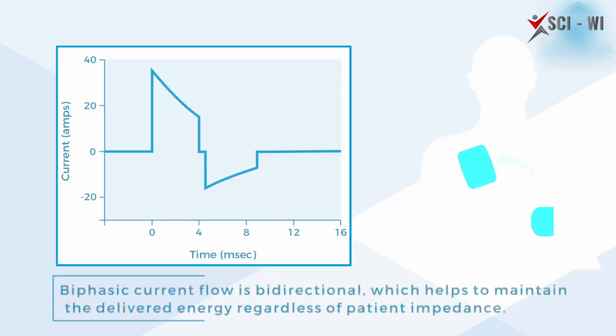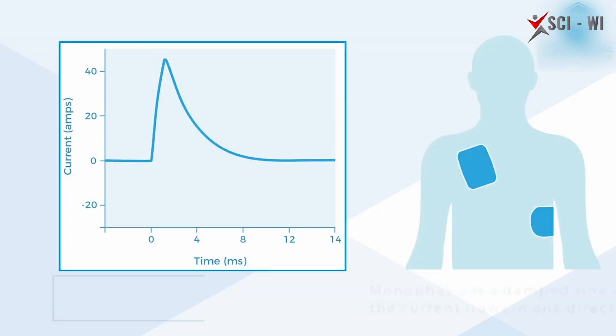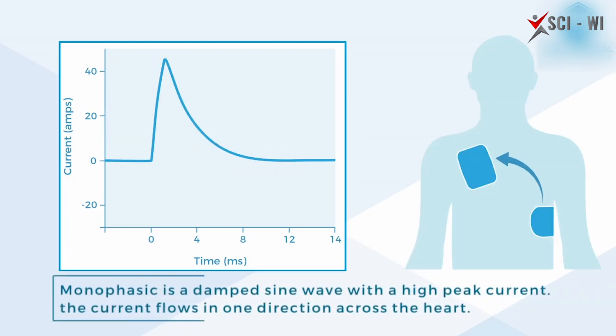In monophasic defibrillation, the voltage of the capacitor determines the energy that is delivered by the pads. The waveform linked with monophasic defibrillation has one peak, which is crucial in determining the success of defibrillation.